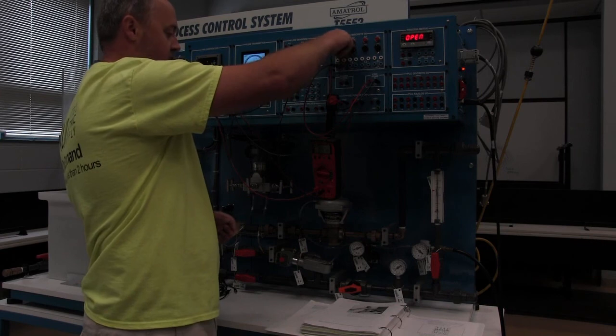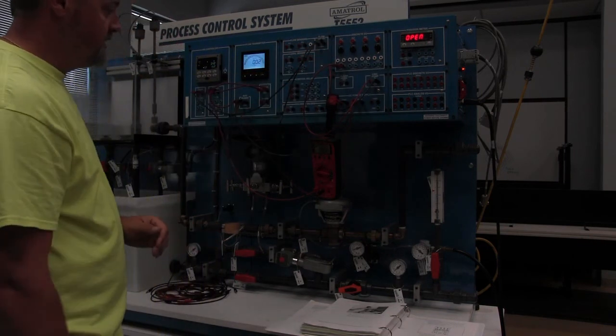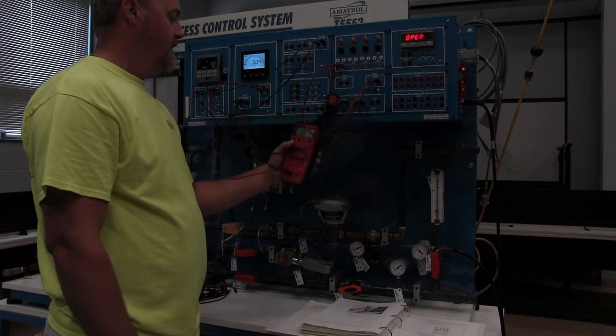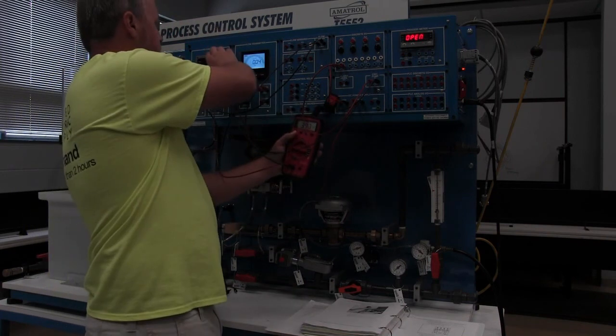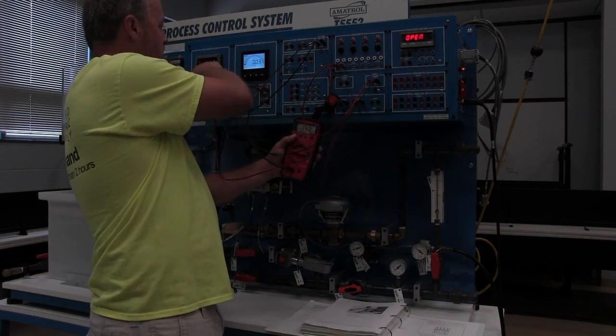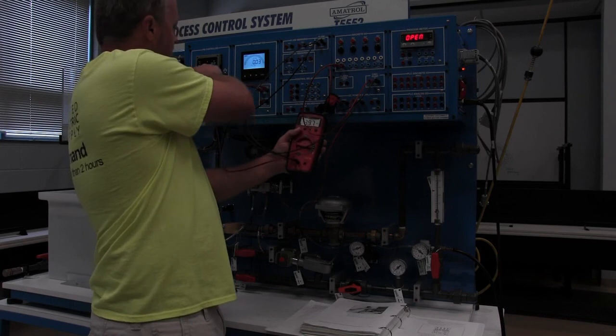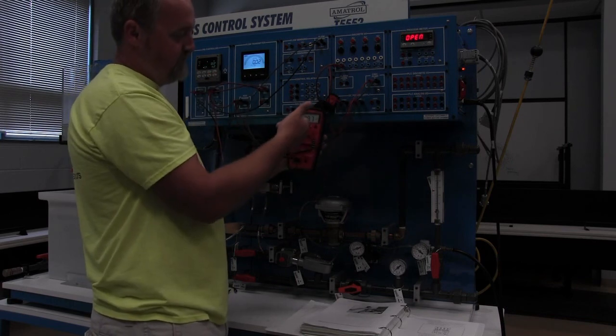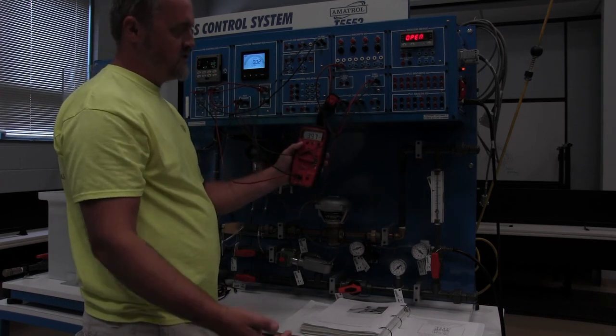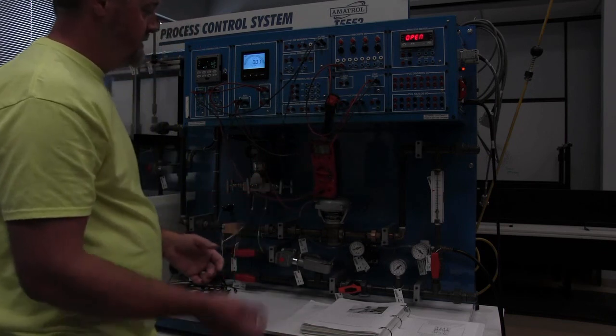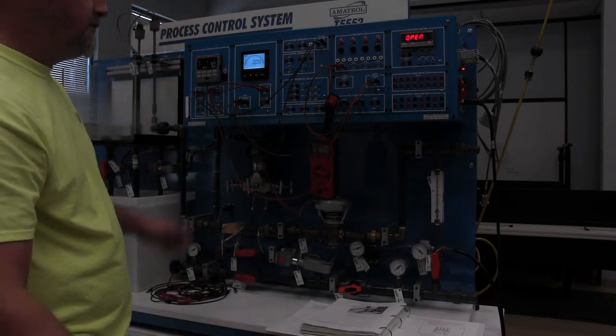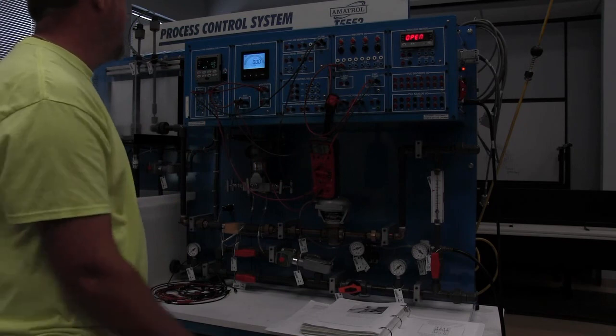So we'll go ahead and shut that down. Once we shut that down, we should notice that because this device is shut down, we still haven't got to where we need to be. We're at 3.97 milliamps, which is basically 4 milliamps, because it's saying, hey, my set point's a 1.5, I'm not meeting it, give me everything you got.